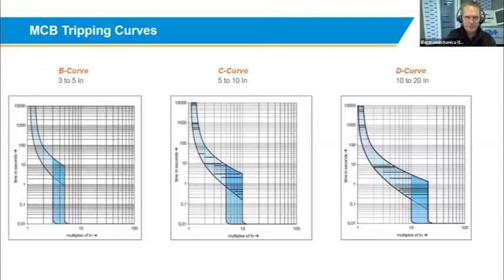Okay, then getting to the different tripping curves that are available from Hager. The three tripping curves here are a B curve, where we talk about 3 to 5 times IN, the C curve, which is 5 to 10 times IN, and then the D curve, which is 10 to 20 times IN. And what does this mean? Why do we have different tripping curves, and what does this 3 to 5 and 5 to 10 times IN mean? On the next slide, I have put all three of these tripping curves onto one another and combined them into one slide. And I'll give you an indication of what the meaning of all these different curves is.